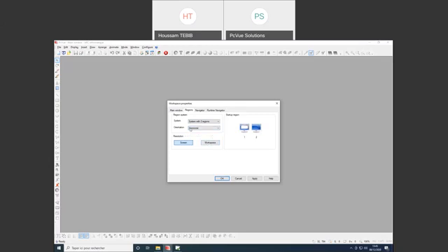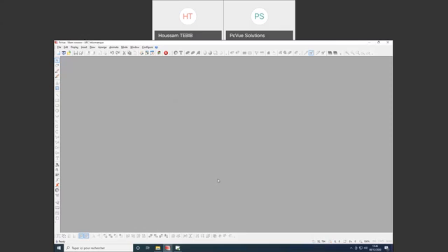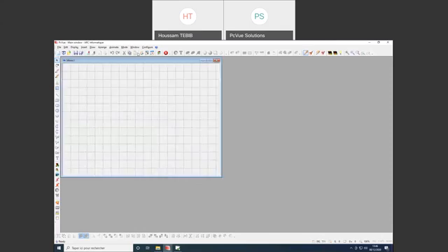Then I will choose horizontal, and for the resolution I will choose screen resolution. Then you have to choose a startup region: you have to choose if screen 2 is the startup region or screen 1. So for my example now, I will choose screen 1 as the startup region. When I finish, I will apply and OK. Then for this demonstration, I have only one screen. So we'll consider the first screen is on the left side, and screen 2 is on the right side.